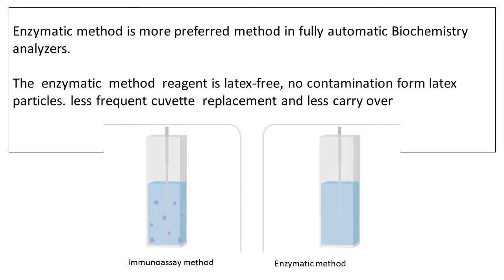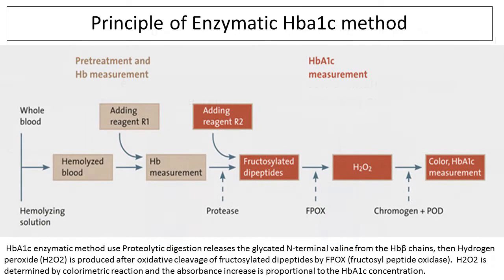The enzymatic method also offers less frequent cuvette replacement and less carryover. The principle of the enzymatic HbA1c method uses proteolytic digestion to release the glycated N-terminal valine from the hemoglobin beta chains. Then hydrogen peroxide is produced after oxidative cleavage of fructosylated dipeptides by fructosyl peptide oxidase. The hydrogen peroxide is determined by colorimetric reaction, and the absorbance increase is proportional to the HbA1c concentration.